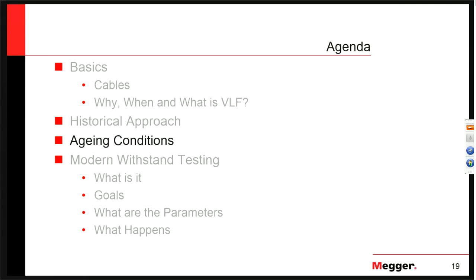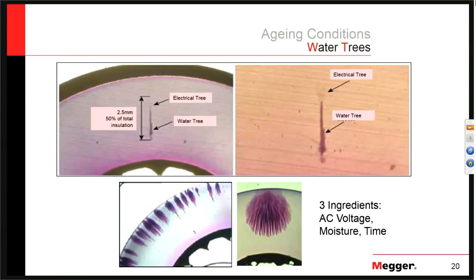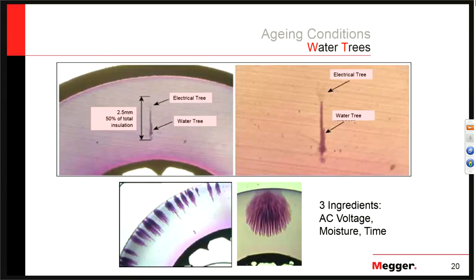What are the aging conditions we keep talking about? Primarily, we're talking about water trees. Almost every cable will develop them — some are more susceptible than others. We classify them into two groups: small distributed water trees, which are an issue but not necessarily critical; and one very large tree, which is the one we're really concerned about — the kind that can cause problems in the very short future.